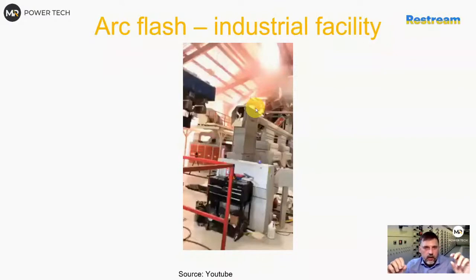When you do the arc flash study - it's one word, but it means we do short circuit current calculation, equipment evaluation, protection check, sometimes load flow, which isn't really required but you might do it as well, and arc flash. Then you make recommendations to fix the problems, and redo the same calculations.